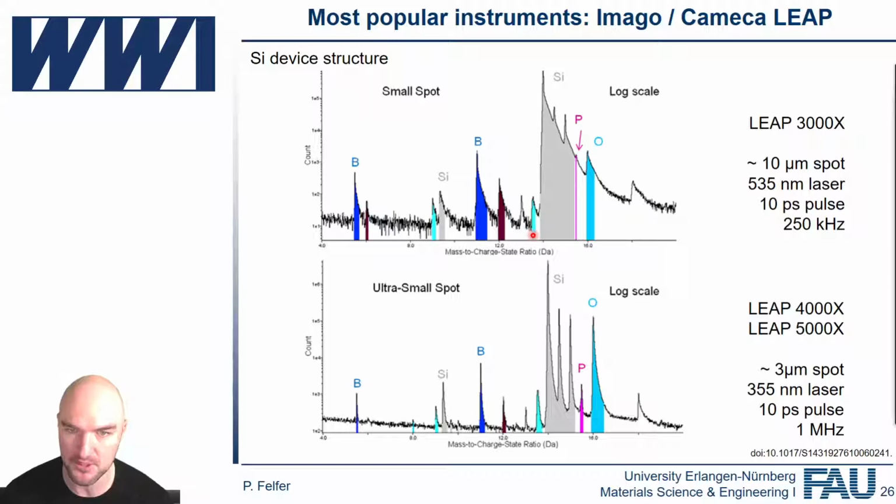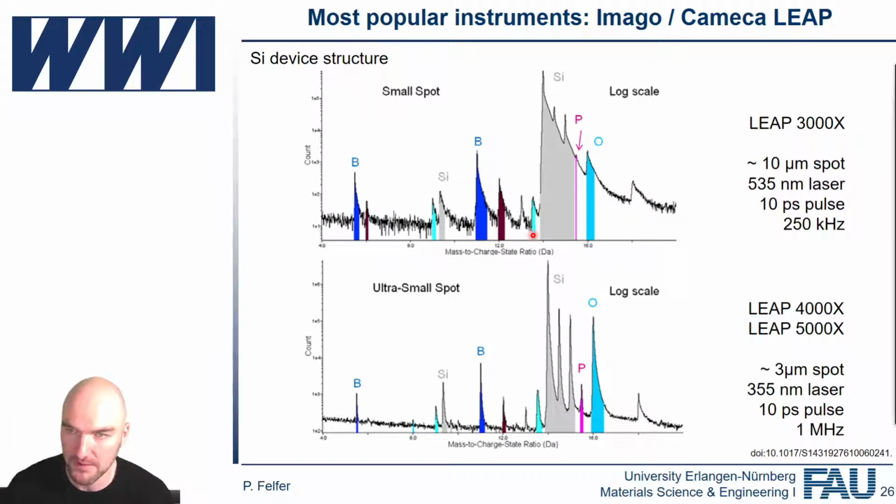So in the Cameca atom probes, the focus position is controlled by just moving the focal spot around and looking at where you get the highest field evaporation, the highest flux of atoms. Because then it's sort of ideally positioned, if you will. That is one way of doing it. Then the colleagues in Stuttgart essentially have made the laser a confocal microscope. So they can position the laser using essentially confocal microscopy. Our colleagues here in physics that do very similar experiments, they essentially have complete imaging optics to do that. So it always depends on what your setup is.